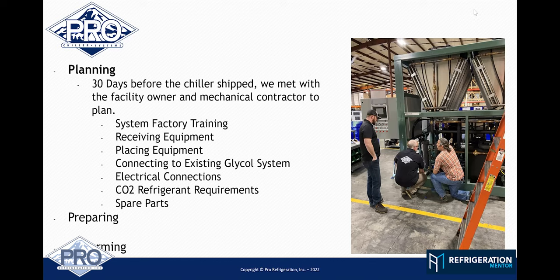Thirty days before the chiller shipped, the facility owner and their mechanical contractor came out to the factory for authorized training on the system. We went through how to receive and place the equipment, and how to make connections to the existing glycol system. Since the facility is in operation, they can't just shut down for five days to make the changeover, so we had to plan how to tie into their system while keeping 100% uptime. A package system allows you to plan for that.